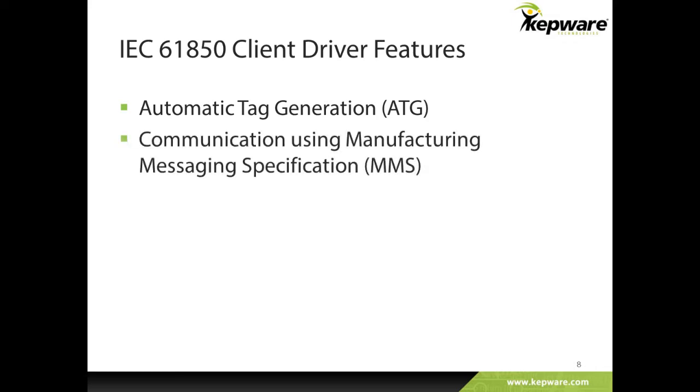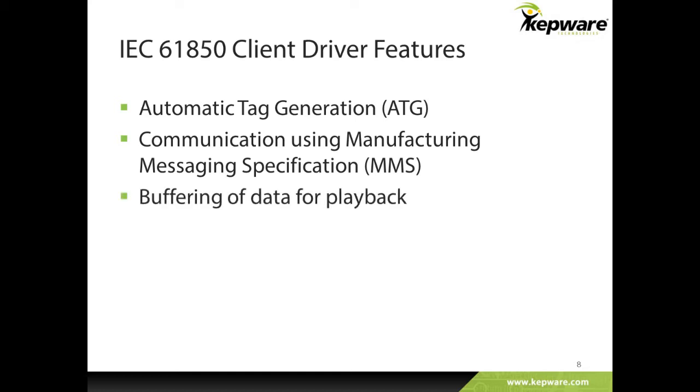The IEC61850 MMS client is a premium driver available for KepServer EX. The driver supports automatic tag generation by querying the device or loading the substation configuration SCL file. Communication is facilitated using the Manufacturing Messaging Specification or MMS within the IEC61850 protocol. Data updates may be received by polling device at a set interval or using report control blocks for unsolicited data. Multiple data updates can be buffered in the server cache and played back to the client to prevent data loss in between scan intervals. Finally, the IEC61850 MMS client streamlines the setup of the control model for the device.